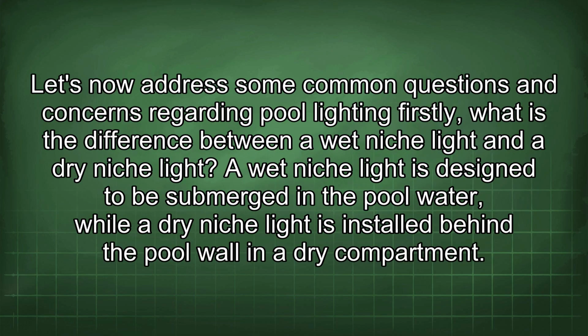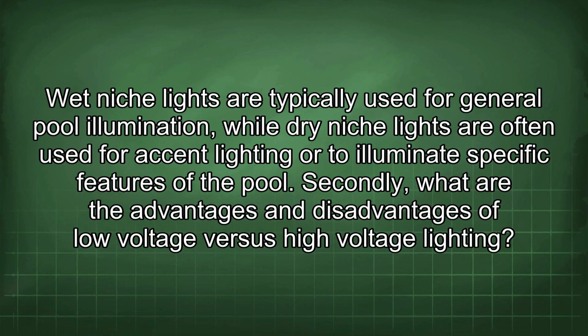Let's now address some common questions and concerns regarding pool lighting. Firstly, what is the difference between a wet niche light and a dry niche light? A wet niche light is designed to be submerged in the pool water, while a dry niche light is installed behind the pool wall in a dry compartment. Wet niche lights are typically used for general pool illumination, while dry niche lights are often used for accent lighting or to illuminate specific features of the pool.